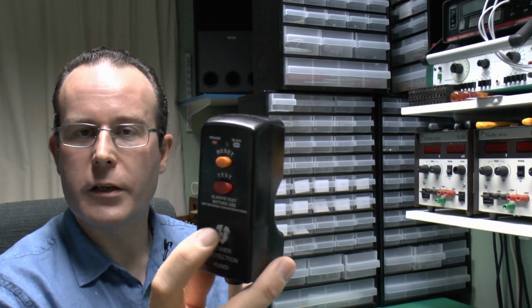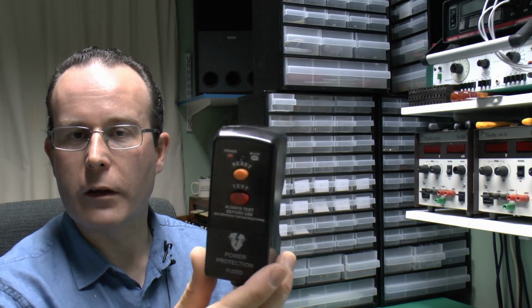You can also get these in a similar style with the plug there and a socket on the back, so you can of course use that with any other appliance you might want to. And these devices are only there for one purpose, and it's to disconnect the supply in the event that current goes to places that it shouldn't, such as if someone touched a live wire, or you slashed through the wire of your hedge trimmer and it trailed in the grass. And these are also the devices which are primarily there to protect people rather than the installation itself.